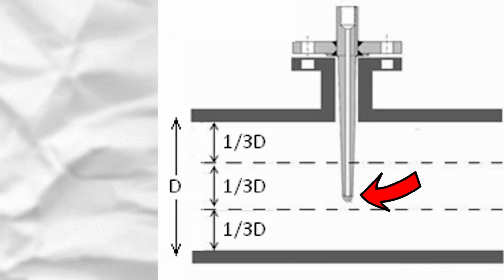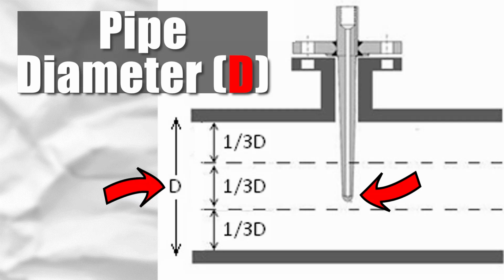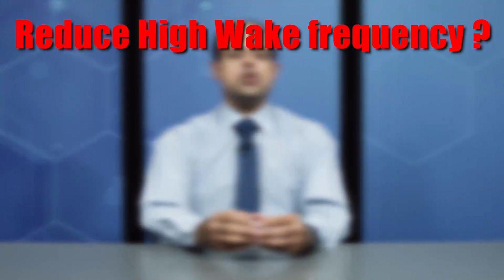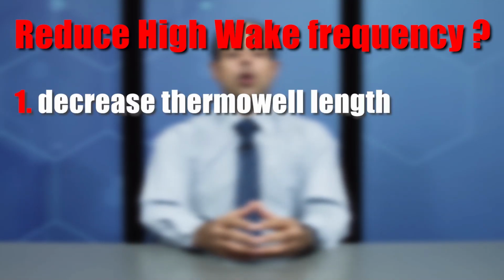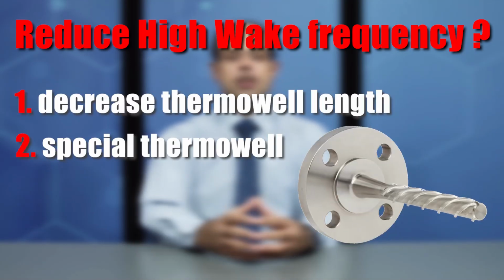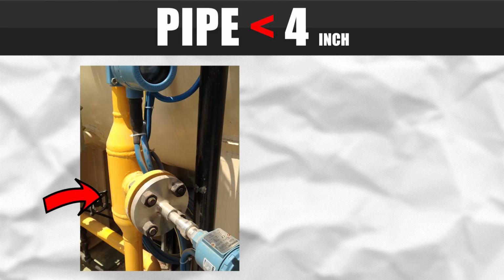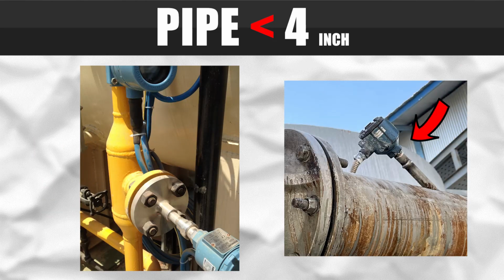Moreover, the tip of a thermowell must be located between 1/3 and 2/3 of the pipe diameter in order to measure accurately. A way to reduce high wake frequency is to decrease the length of the thermowell, or you may even apply a special thermowell design. Please bear in mind that if the pipe size is smaller than 4 inches, you have to expand the line size to install a thermowell. Sometimes installation at 45 degrees is suggested as well.